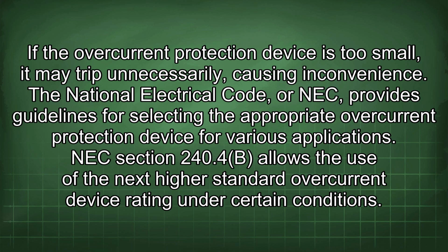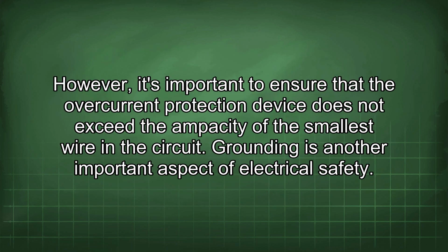The National Electrical Code, or NEC, provides guidelines for selecting the appropriate overcurrent protection device for various applications. NEC Section 240.4(B) allows the use of the next higher standard overcurrent device rating under certain conditions. However, it's important to ensure that the overcurrent protection device does not exceed the ampacity of the smallest wire in the circuit.